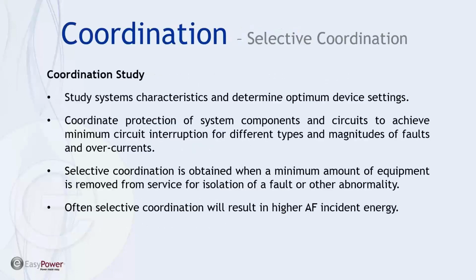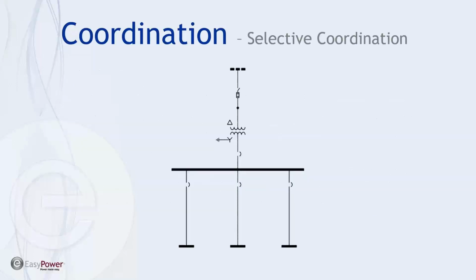Now, the topic of coordination, and specifically selective coordination, is a study of the equipment to determine the optimum device settings such that if it's coordinated, we achieve a minimum circuit interruption for different types of faults and magnitudes. This will allow the equipment or the facility to stay up for the most part and isolate any fault or equipment that's faulty in the most efficient way. Now, the catch-22 here is that often selective coordination will result in higher arc flash incident energy in some parts of the plant, because what we're talking about is a separation in time between the activation of equipment downstream and upstream, where the upstream needs to be slower as a result.